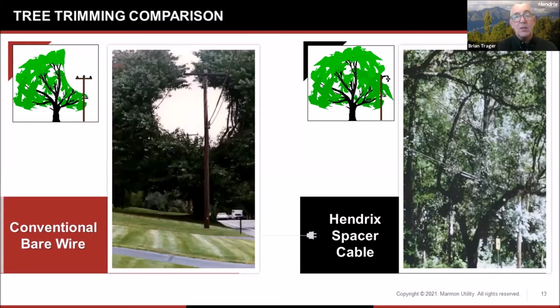We also want to minimize our tree trimming. We're saying that we've got about an 80% reduction in tree trimming and saving fully 80–90% of the canopy. You see on the left, we've got a bare wire. They've cut that thing quite significantly, whereas on the right, we're stringing that spacer cable below the major limbs. We're not having tree trimming. We're not having outages. We're not having dead birds and squirrels. We're getting shade over the tree. We're protecting the houses in the neighborhood from the wind. It's a win-win from a reliability, economics, a safety, and public relations standpoint.